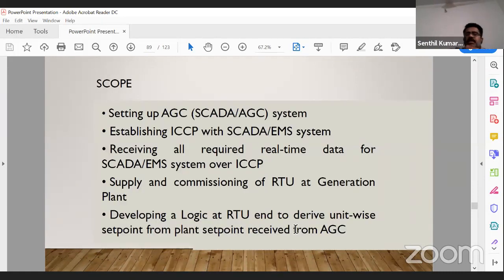What's the scope of setting up the AGC system? Establishing ICCP, the SCADA EMS system, receiving all required real-time data for the SCADA EMS system over ICCP, and supplying and commissioning the remote terminal unit at the generation plant. On both sides, we provide the RTU and the AGC control terminal unit and monitoring system. Based on this provision, we manage the system and pick up the generation easily. We also develop logic for the RTU to drive the unit-wise set point received from the AGC plant set point.